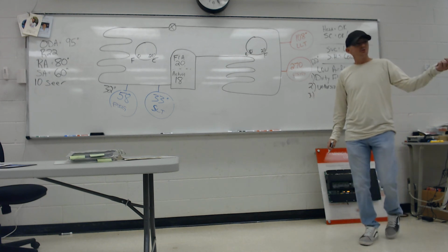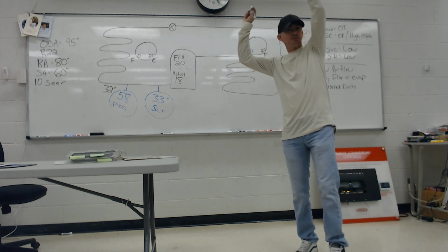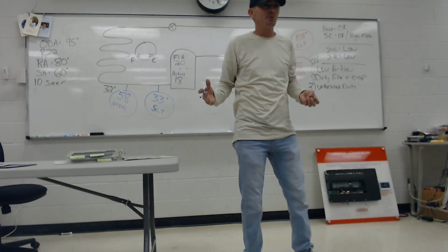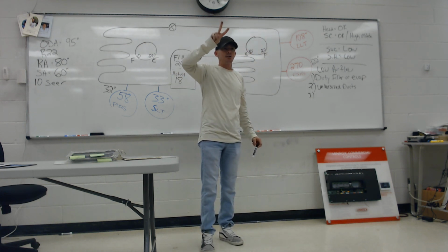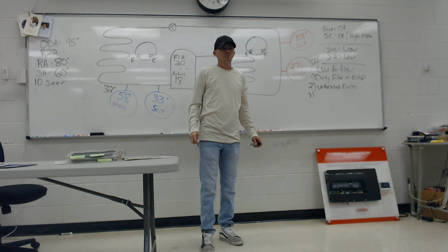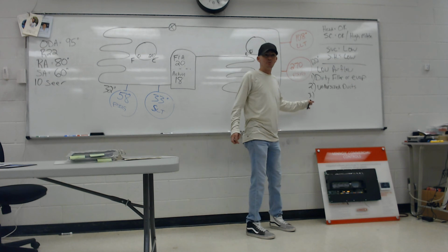Undersized filter grills, right? In the commercial world, a 20 by 20 filter grill fits perfectly in the ceiling grid. Everything gets a 20 by 20. A 20 by 20 filter grill is good for 2 tons, 800 CFM. So a 20 by 20 is only good for 2 tons. Let's keep doing this real quick until we got a couple minutes.